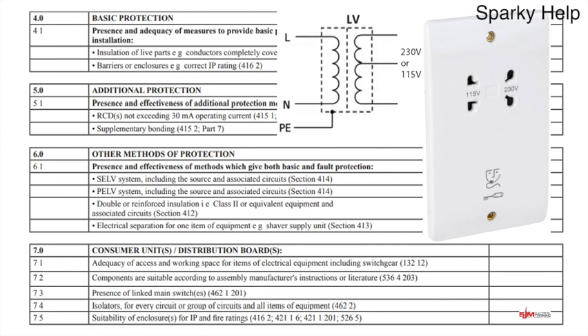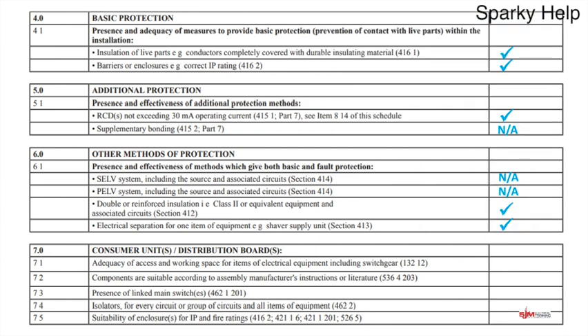Not to be confused with shaver sockets that are single devices, so not a double module like this, but they don't have transformers on. So be very wary if you ever do come across them and they are just single modules, because they wouldn't be allowed in a bathroom because they are just direct connection. Probably going to have one, tick.